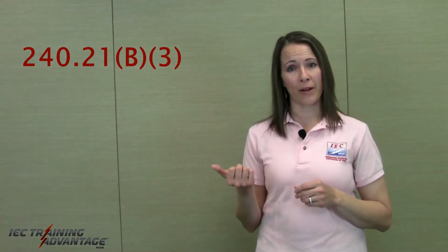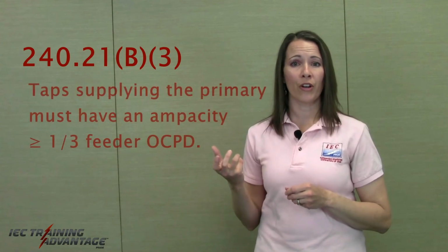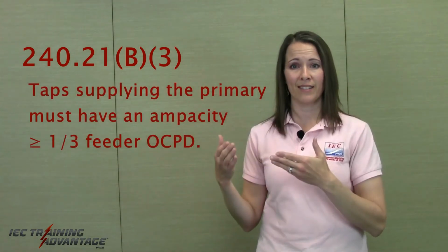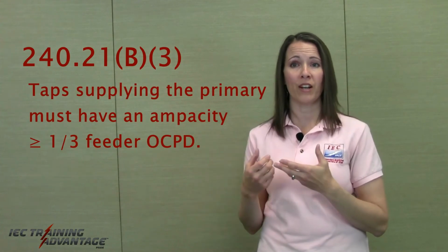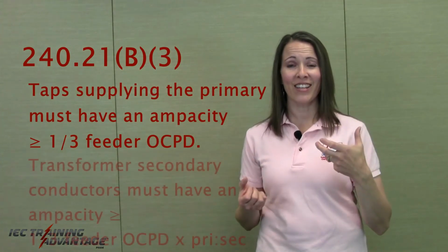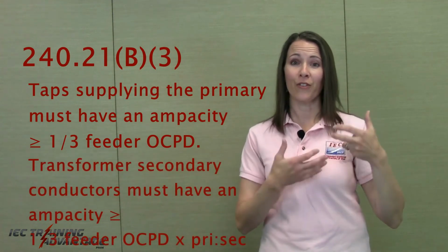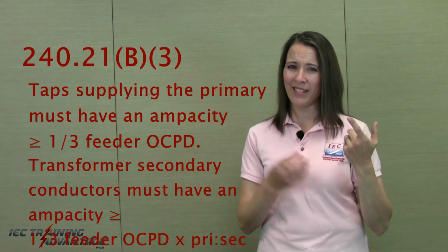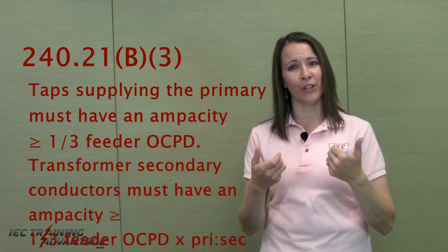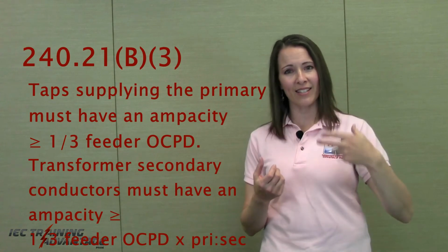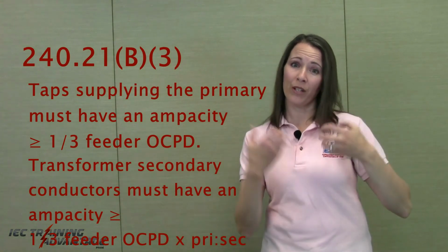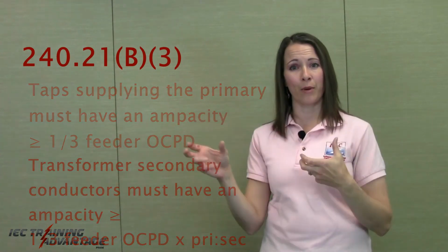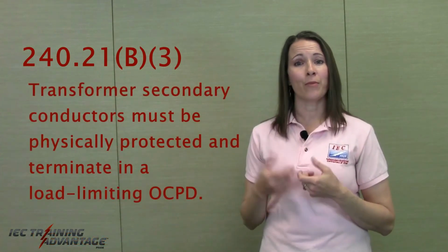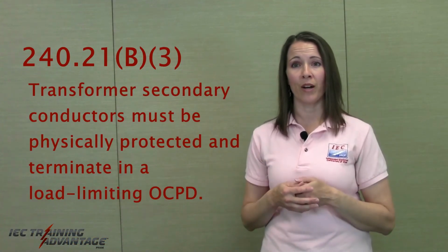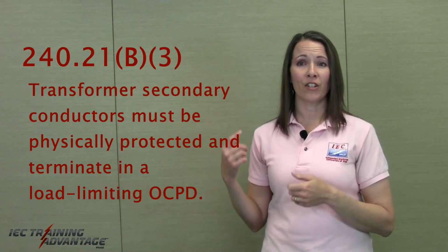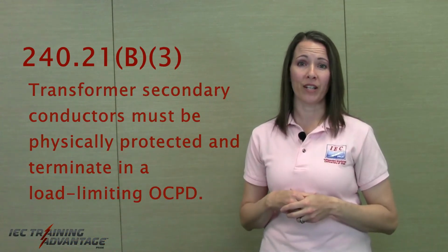Taps supplying the primary must be at least 1/3 of the feeder overcurrent protection device size. Okay, so similar to these rules that we've been talking about already. Secondary conductors have to be at least 1/3 of the feeder overcurrent protection device times the primary to secondary voltage ratio. And all this does is protect these secondary conductors, as they are going to be carrying more current than the primary conductors. Conductors have to be physically protected. We've seen that subsection before. And the secondary conductors also must terminate in a load-limiting overcurrent protection device.